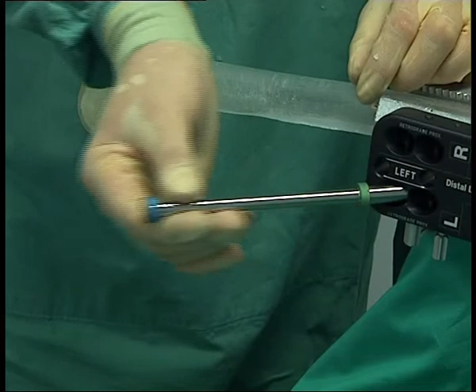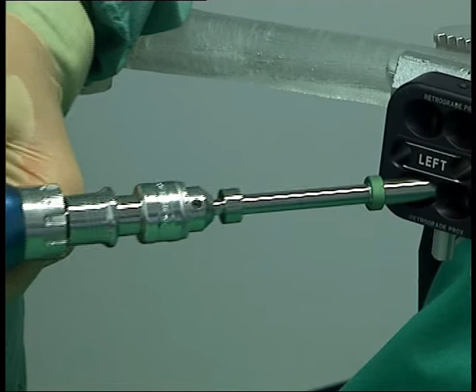Now drill with the 4.8 mm cannulated drill in a clockwise direction. Drilling is continued until the calibration of the measured length is flush with the collar of the blue drill sleeve. As usual, this procedure is performed under X-ray control. After the drill depth has been achieved, remove first the drill while rotating it clockwise and then the blue drill sleeve. Using the 6.4 mm reamer, ream the lateral cortical bone until the reamer strikes the collar of the green drill sleeve. After the required cutting depth is reached, the bit can be removed.